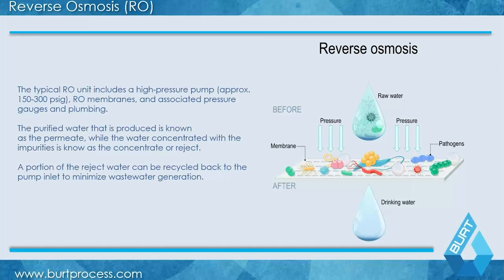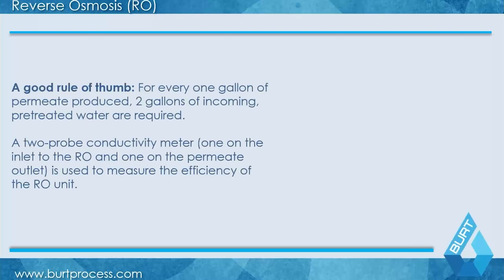Because of how an RO unit operates, you have to have a reject stream — solutes have to go somewhere. A fraction is recycled for water conservation and membrane treatment, and the rest is discharged as waste. The most optimized ROs will have maybe 20% reject, so if I put 5 GPM in, I get 4 GPM out and send 1 GPM to drain. An unoptimized RO is about 50% reject. On a small system that's manageable, but when you're looking at 50 GPM permeate, sending 20 to 30 GPM down the drain becomes very significant.